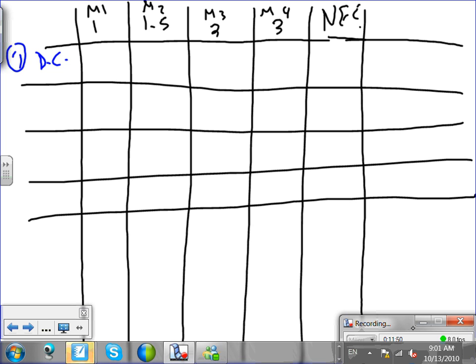All right, let's start, guys, by finding the first thing you do before I even put the calculation. The first thing you do in a problem like this, before you do any calculation, is you need to find full load current from NEC. That's the first step you do. And to find the full load current from NEC, you're going to go to table 430.248. Can you guys go with Uncle Chad to table 430.248?